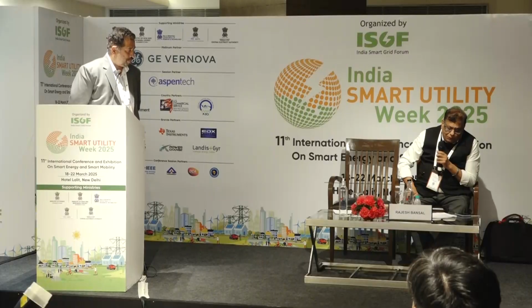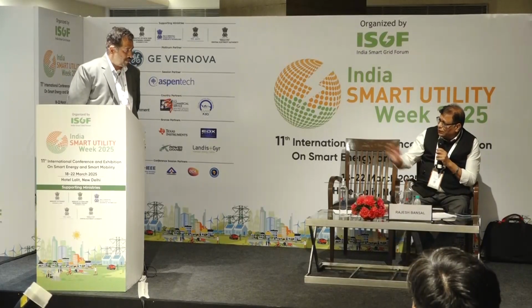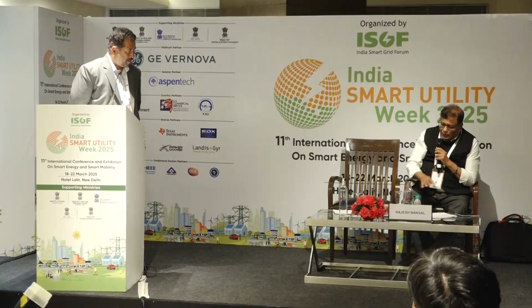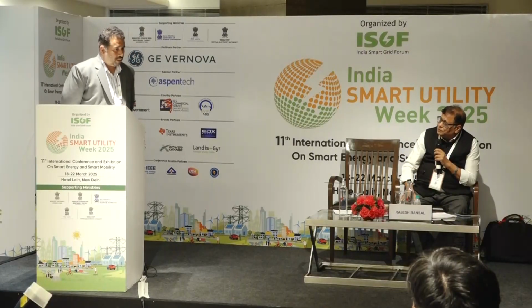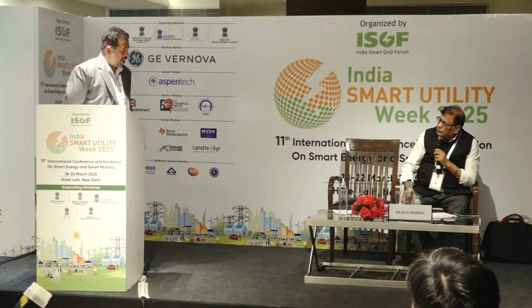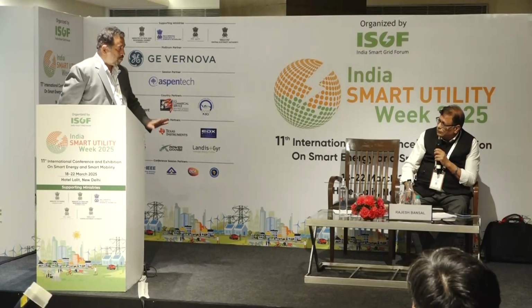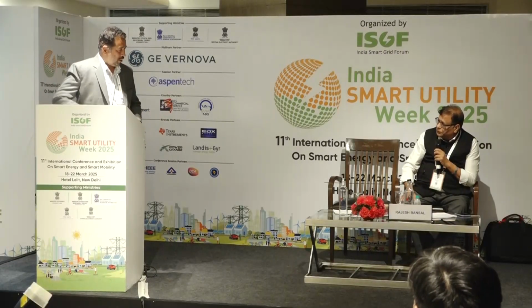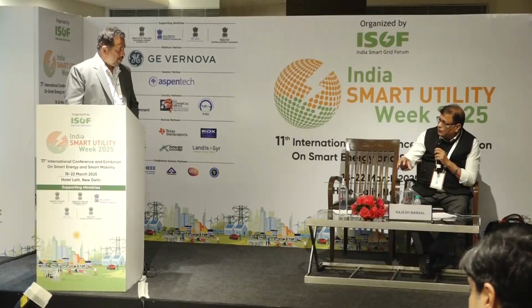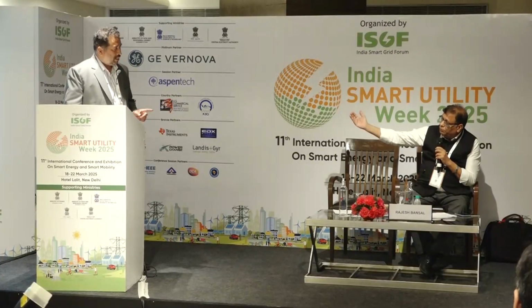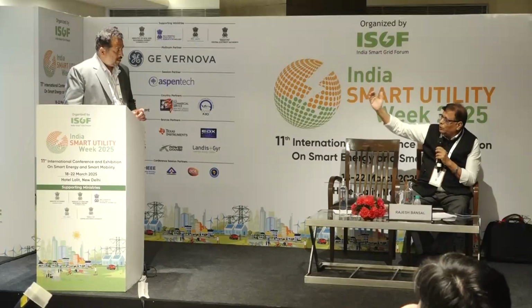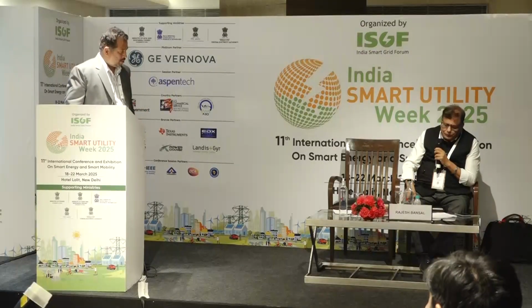When we talk about a fault, there are three related terms: the occurrence of the fault, the location of the fault, and the type of fault. And the tripping occurs somewhere else. Yes, the fault happens in one place, the tripping happens in another. So are you able to detect all three - where it happened and how it happened? Currently we are recording outages at the feeder level, RMU level, and DT level, but only partially, not fully. That's the tripping level. But which pole on the LT feeder it happened at, the 5th or 8th pole, that is not getting recorded.